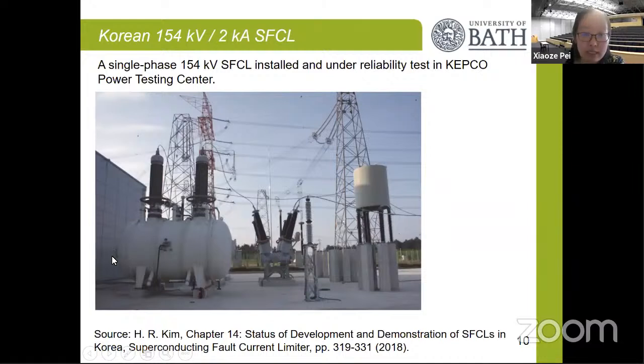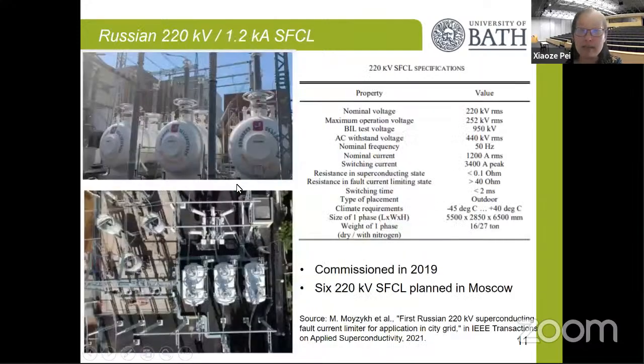So what you can see here is the cryogenic system, which is a cryostat filled with liquid nitrogen. And the top bushing here is the current leads from the room temperature down to the cryogenic temperature of the superconducting tape. This is one of the key challenges in the design. Firstly, it needs to take the temperature gradient from 290, like 300 Kelvin at room temperature, down to 70 or 60 Kelvin. Secondly, it needs to transport a very high current value. And thirdly, there is a triple connection between the vacuum and the environment. So there is a lot of development around the bushing design in this area.